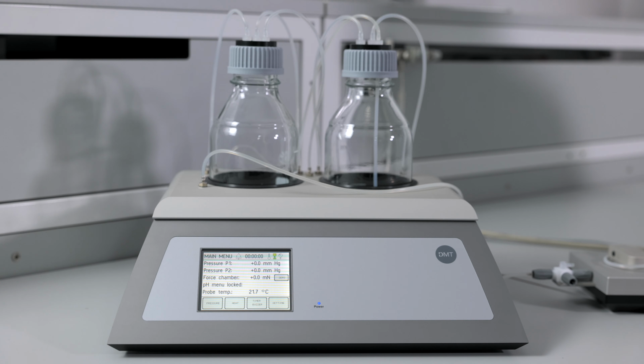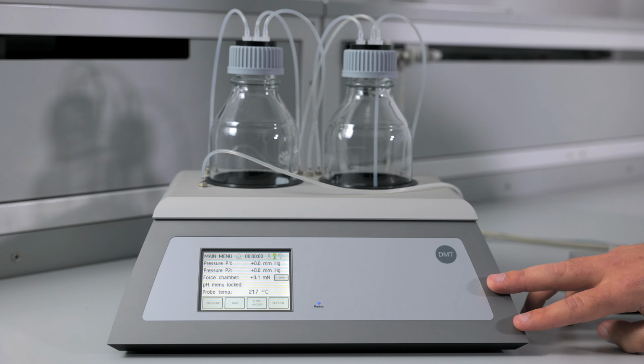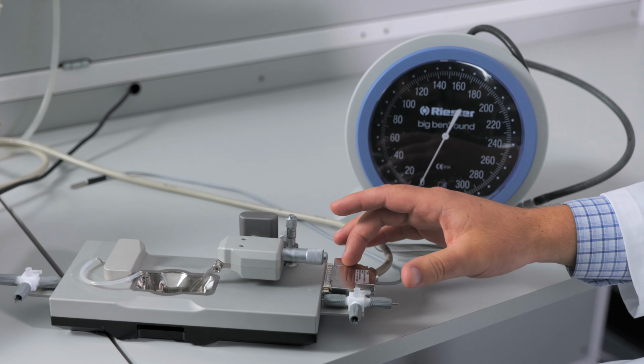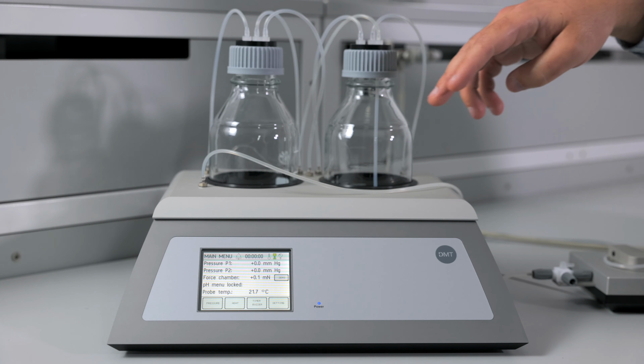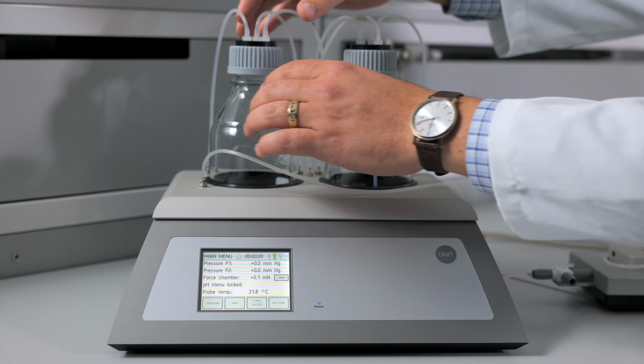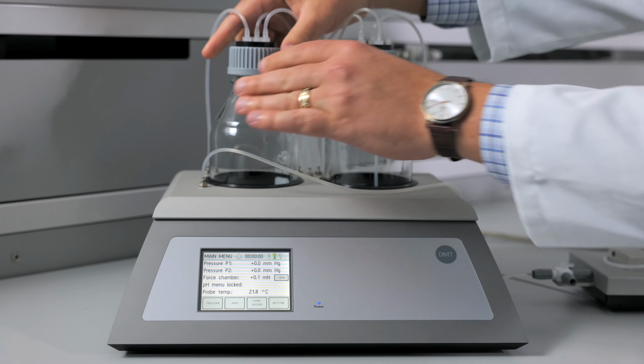In order to set up the system for the pressure calibration, you want to make sure that the interface is powered on and connected to the chamber, that you have air in all the lines, and the P2 bottle cap is securely in place.